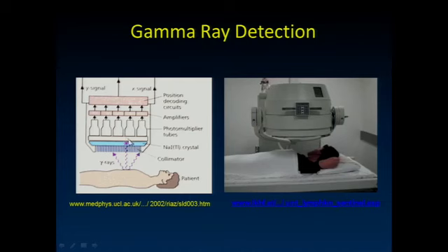When we give a radiopharmaceutical to a patient, we end up with a distributed source of radiation. So we really need to make sure that we only detect gamma rays traveling in a particular direction. Otherwise, our image is just going to be an absolute blur of activity traveling in all different directions. So it's really the collimator that acts as the lens to focus the radiation so that we're only accepting it along a particular direction.